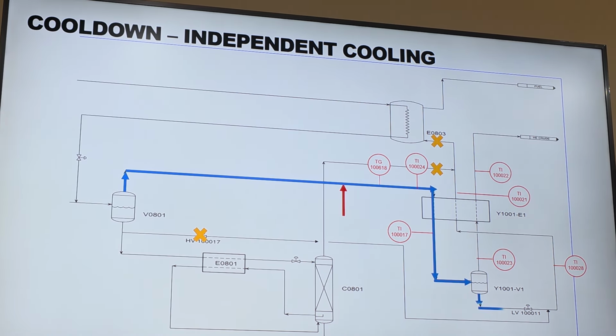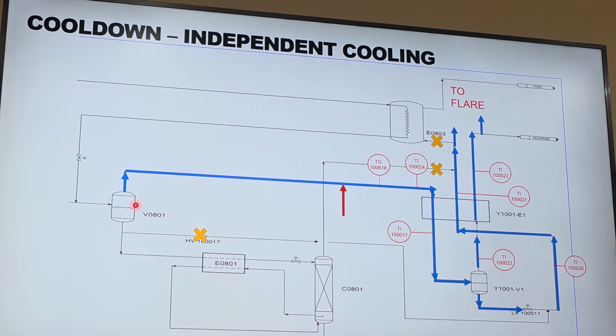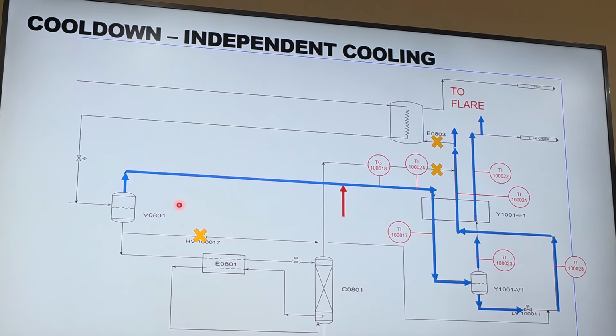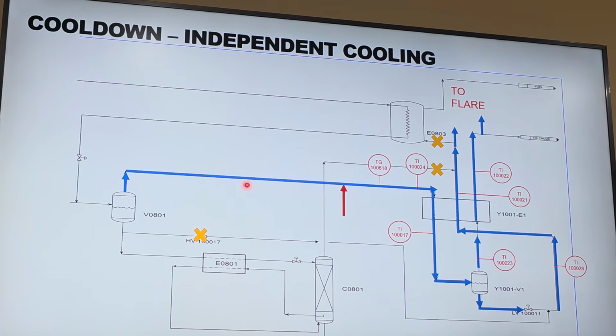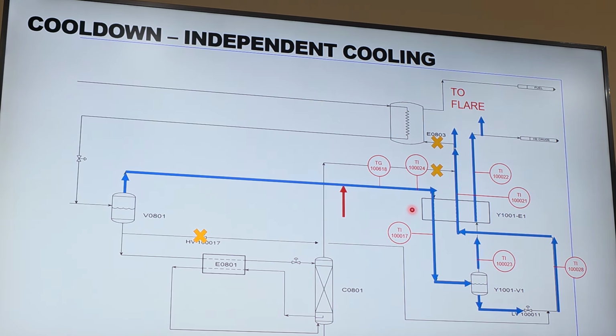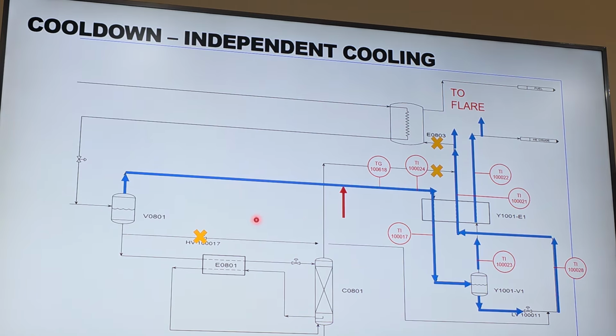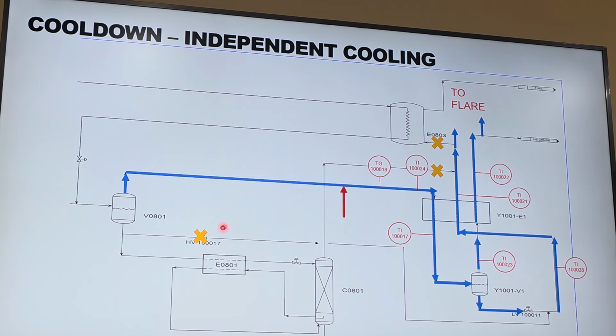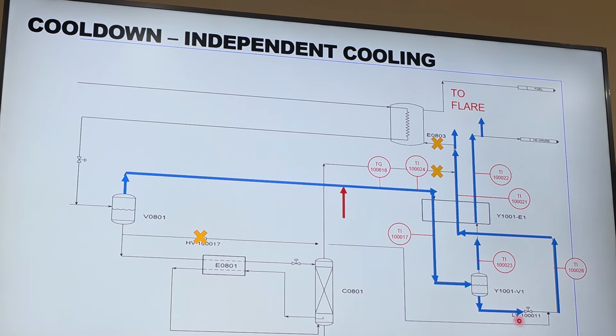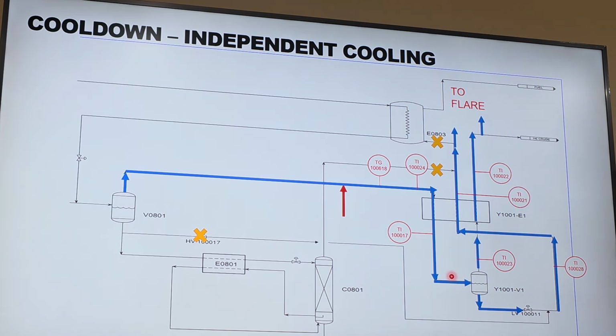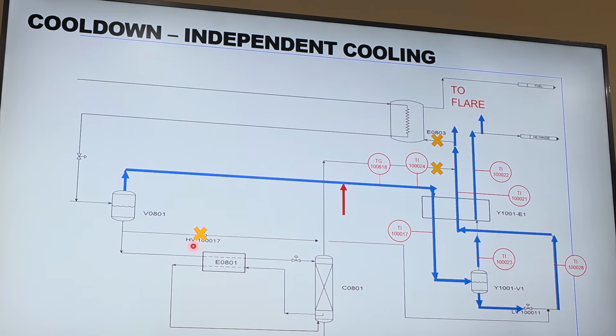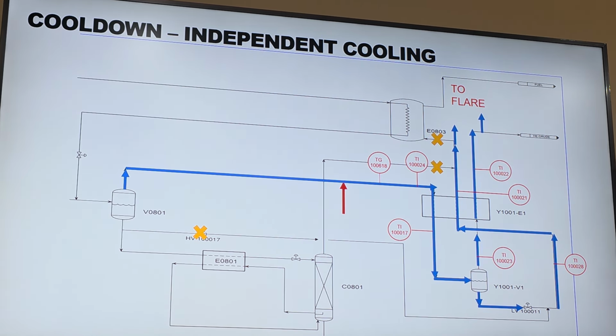So, as before, if you're trying to cool down and you need operational gas, you're just going to use the gas from there, similar to a cold defrost, and you're going to be blending cold gas in with this defrost gas. Then as you get down, you can open this back up to begin feeding liquid from the flash drum to assist in the cool down, because this needs to be negative 180 roughly. So you need to get quite cold. You might need to assist with refrigeration with this hand valve 17. Yeah, that's what the other classes said.